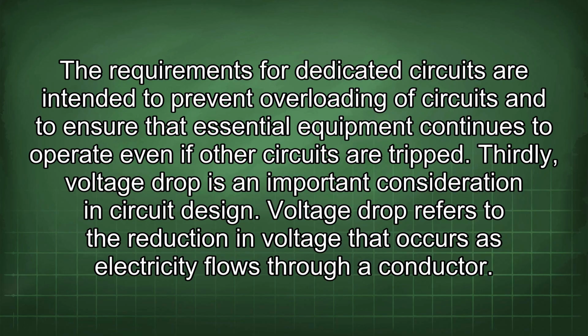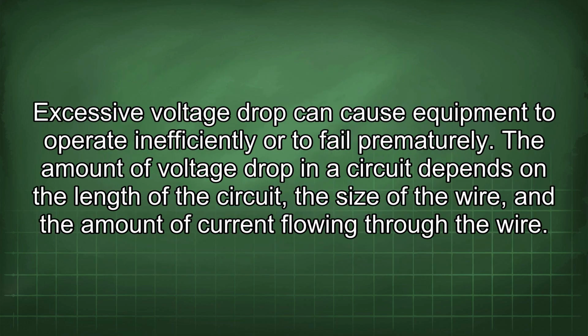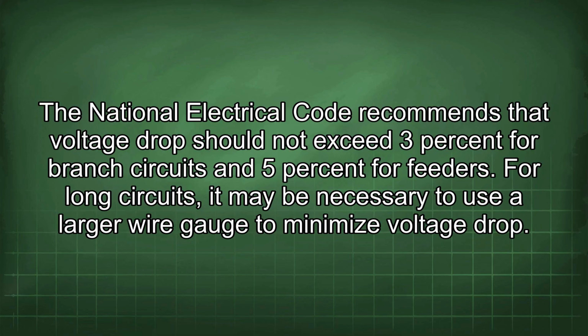Thirdly, voltage drop is an important consideration in circuit design. Voltage drop refers to the reduction in voltage that occurs as electricity flows through a conductor. Excessive voltage drop can cause equipment to operate inefficiently or to fail prematurely. The amount of voltage drop in a circuit depends on the length of the circuit, the size of the wire, and the amount of current flowing through the wire. The National Electrical Code recommends that voltage drop should not exceed 3% for branch circuits and 5% for feeders. For long circuits, it may be necessary to use a larger wire gauge to minimize voltage drop.